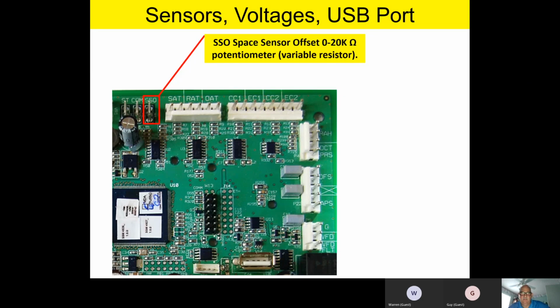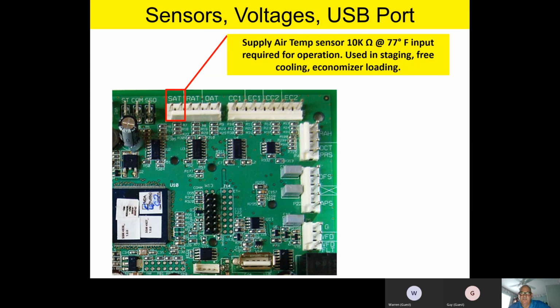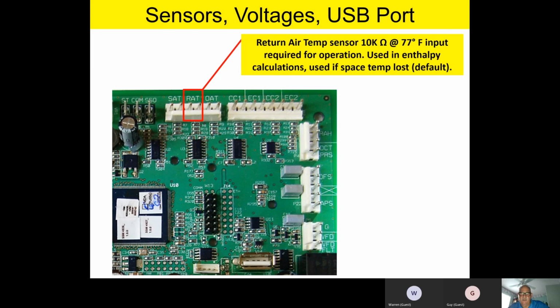Right next to that, you have a 2-pin input-output, and this is a supply air temperature sensor. Again, 10,000 ohms at 77 degrees. It is required for operation. So this is a supply air temperature sensor that comes from the factory hooked up on the unit. Right next to that is a return air temperature sensor. And again, this is required for operation, and it's going to be used in enthalpy calculations. It will also be used if you lose your space temperature. So if you lose the space temperature sensor, the unit will default.